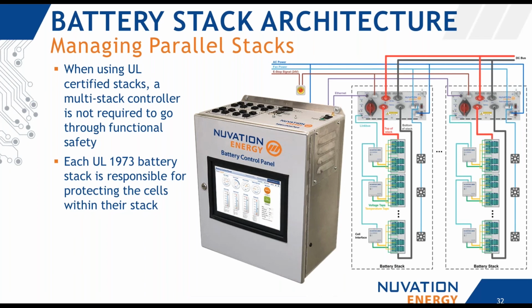So to explain a bit about that, a multi-stack controller, in addition to aggregating how those individual stacks are performing, is also going to make decisions about which stack connects to the common DC bus, as well as presenting that single interface to a 9540 energy controller. But since the BMS in each stack that's connecting to the DC bus is deciding if it's safe to do so, it's going to prevent an unsafe connection. It also autonomously disconnects from the bus if a fault occurs. And so because of that, the multi-stack controller isn't part of that safety path.